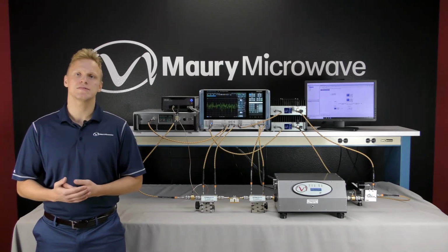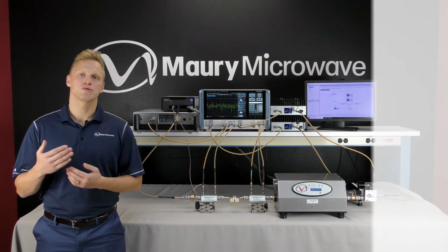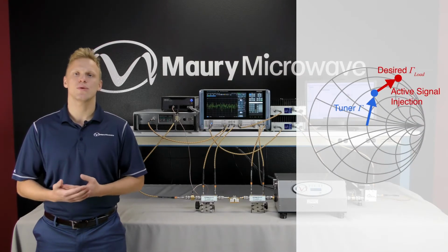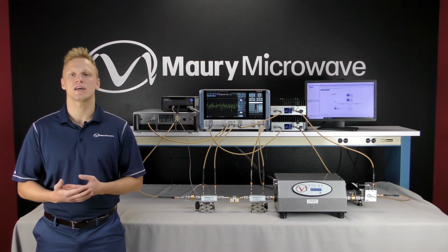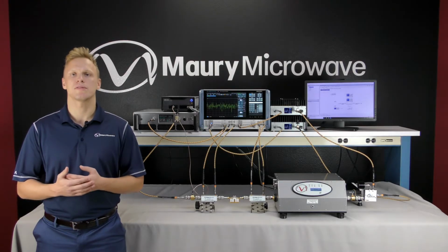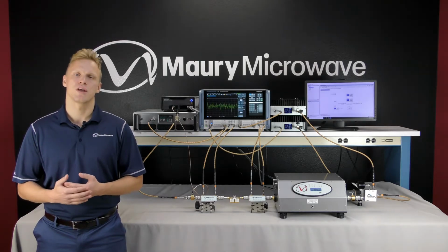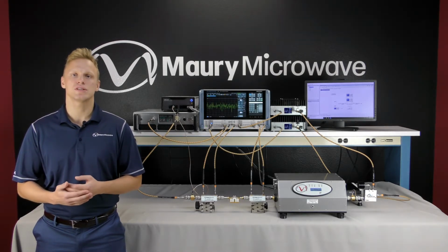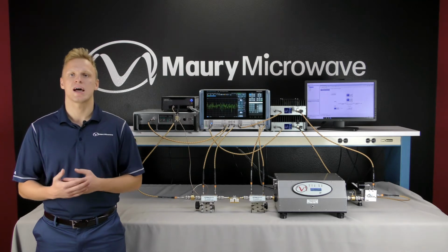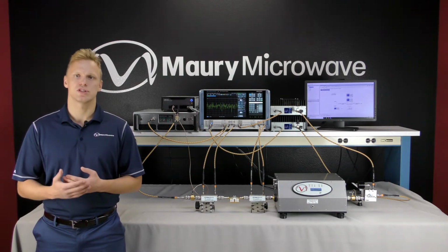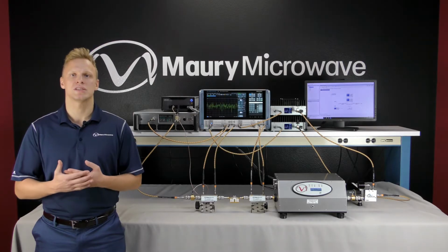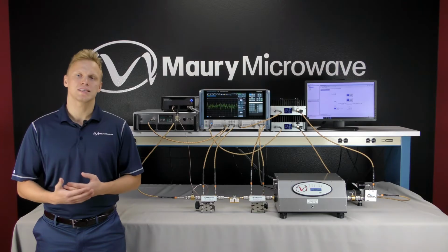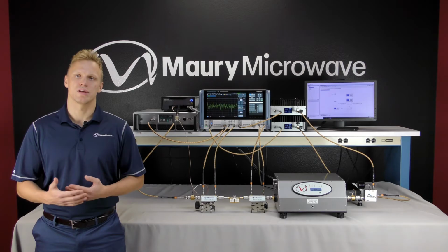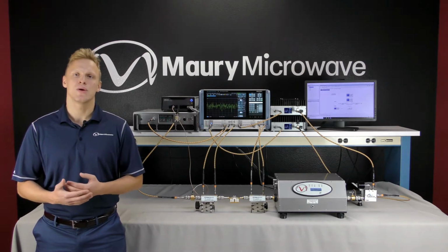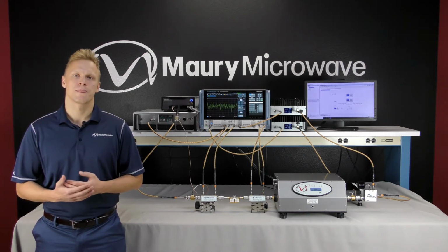The combination of passive and active load pool techniques enables load reflection coefficient synthesis anywhere within the Smith chart by using the passive impedance tuner to pre-match the device under test and to reduce the required load amplifier power for active signal injection. Alternatively, passive impedance tuners can be used to control the device impedances at the fundamental frequency, while active injection is employed to tune the load impedances at harmonic frequencies. The latter configuration is easily achieved with a Rohde & Schwarz 43 series ZNA with an enabled 4-source option.